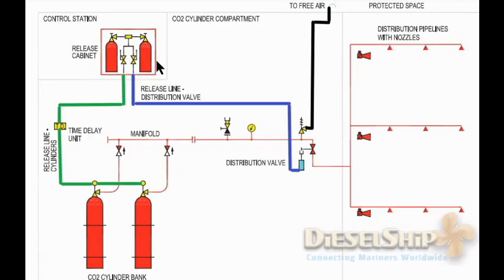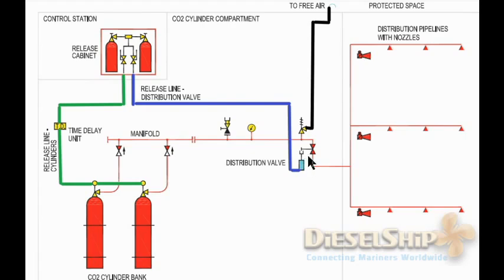The release cabinet has two pilot cylinders enclosed inside a cabinet with a door. Once the door is opened, it gives audible and visual alarm and may also trip ventilation fans and stop fuel pumps — it varies by ship, but it must definitely give audible and visual alarm and stop the ventilation fans. We have two bottles, but we always use only one; the other is a spare. There is a valve to open, and then two valves: the green line opens the main CO2 bottle valve mechanism, and the blue line opens the main distribution valve inside the CO2 room.